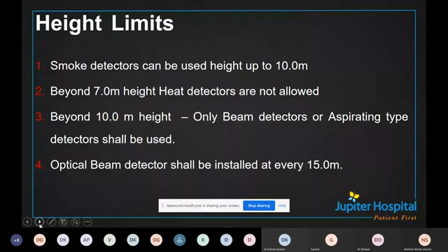And beyond 10 meter height, only beam detectors and aspirating type detectors shall be used. Optical beam detectors shall be installed at every 15 meters. So this is for height limits, what is there for smoke as well as for optical beam detector. Now, choice of detectors. Computer or IT centers or other electronic equipment which have high value should be protected by smoke detectors or a combination of smoke and heat detectors. Heat detectors are suitable in areas where heat producing equipment is present, like kitchen and pantry. And an LPG gas leak detector can be used in the kitchen.